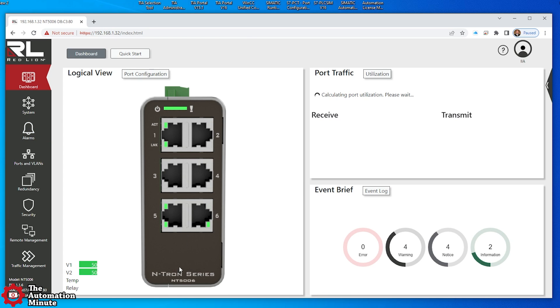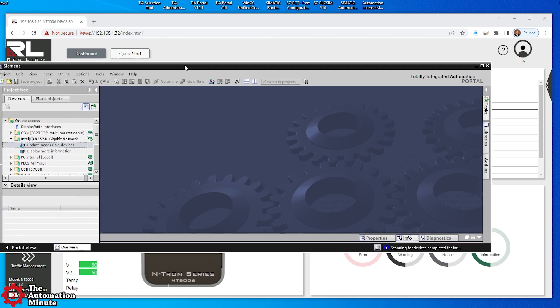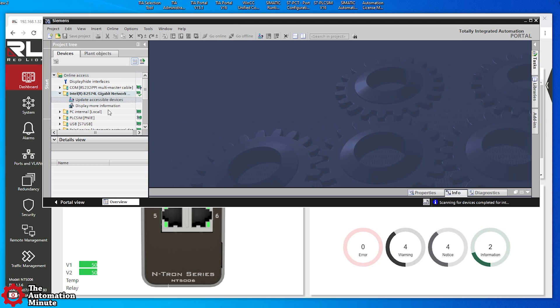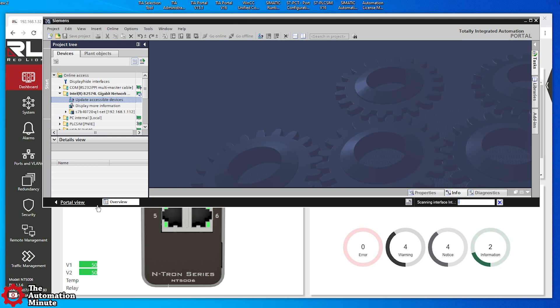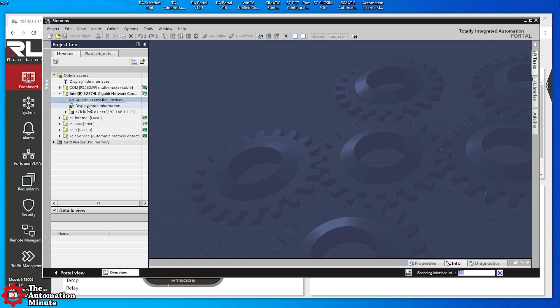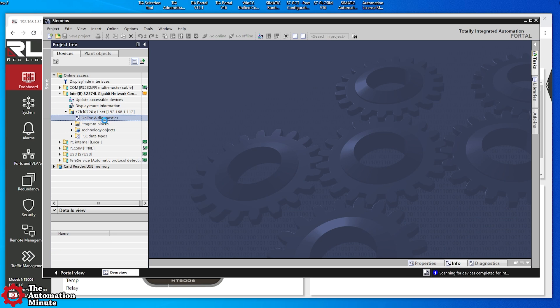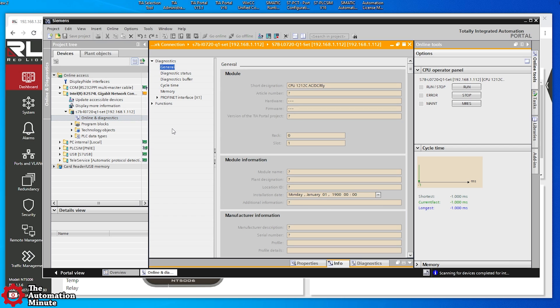All right, let's see if it's working with our PLCs here. So I got TIA Portal open. Let's do an update accessible devices here. And you can see it found my S7-1200. And now I'll go to online diagnostics. And let's see if it connects. Yep, so we're good there.